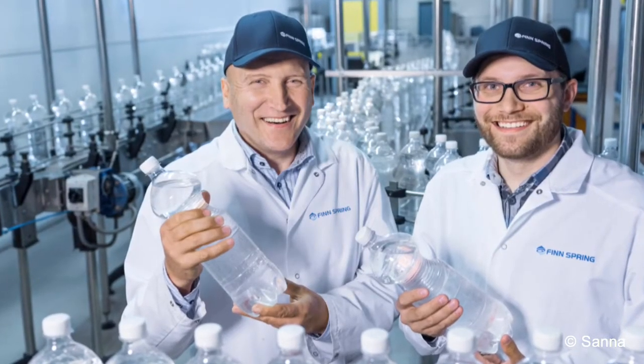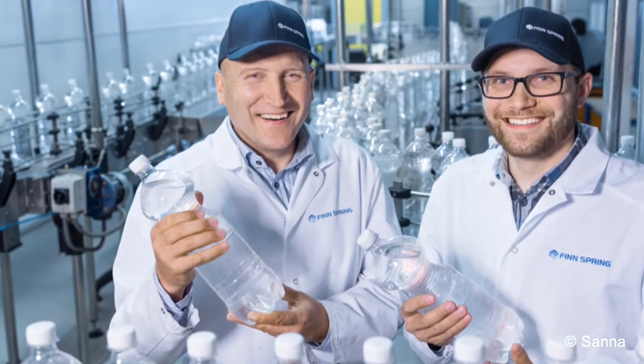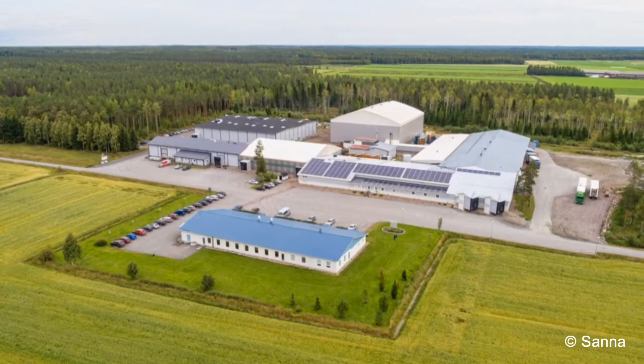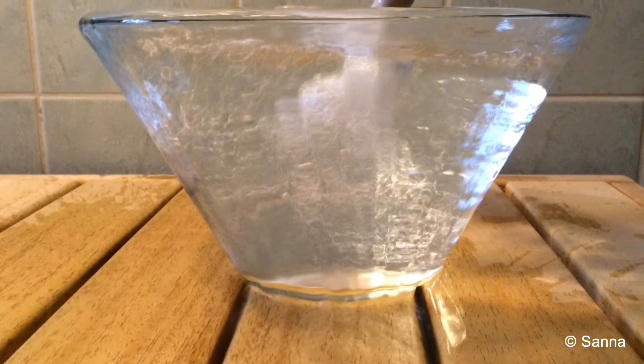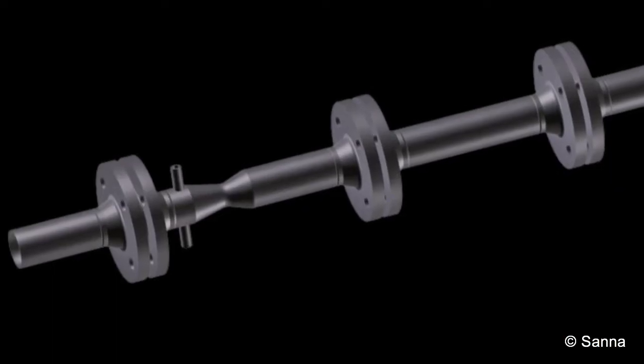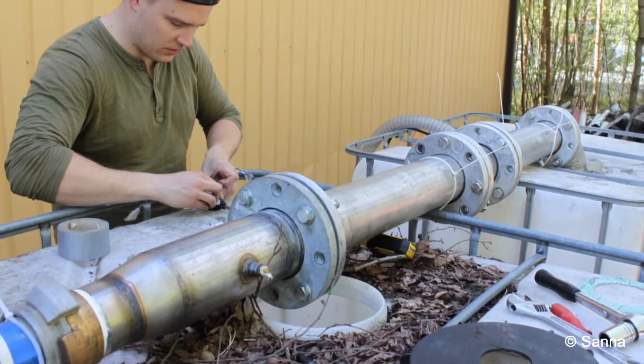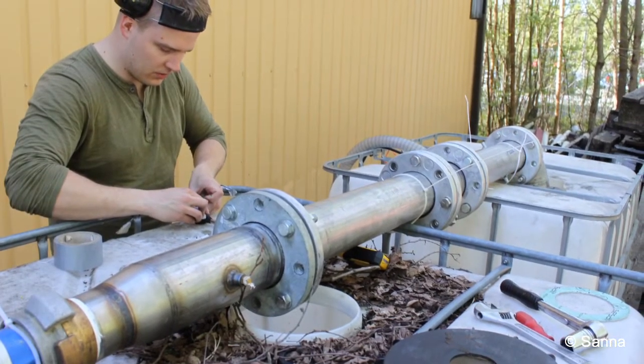Finn Spring is the largest spring water manufacturer in Finland. Finn Spring has chosen OxTube as part of its large effluent treatment process. OxTube mixes effluent from different sources into a homogeneous solution and raises the level of dissolved oxygen close to the maximum in a few seconds. The dissolved oxygen improves the efficiency of the further treatment process and helps to reduce the amount of COD in effluent. OxTube requires no additional energy apart from a separate pump, and at times it even works with natural suction.